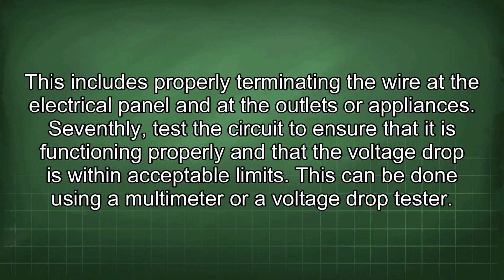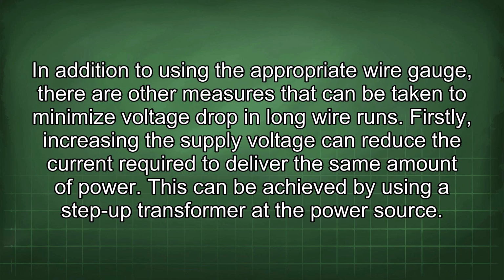This includes properly terminating the wire at the electrical panel and at the outlets or appliances. Seventhly, test the circuit to ensure that it is functioning properly and that the voltage drop is within acceptable limits. This can be done using a multimeter or a voltage drop tester.